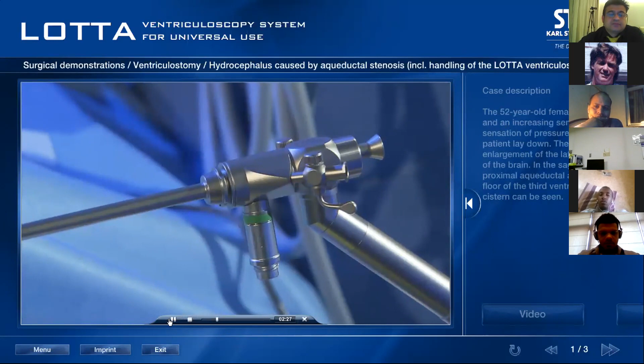However, in a therapeutic scope, because it has a working channel, we have changed 0 degree to 6 degree. Why we have done that? Because when the surgeon is putting an instrument, the issue in an endoscopic image is you are working in 2 dimension. I mean, you are seeing in 3D but working in 2D. So when you are working in 2D, you are not able to get a depth perception. So when you insert the instrument, which is just coming at the tip, the surgeon has to wait literally 1 centimeter, the instrument comes out, and then you can see the instrument has come out. So that depth perception is missing. So it is important to have depth perception. So we moved it to 6 degrees. So the moment the instrument comes out, it gives you a further extra angle of 6 degree laterally, and you can see your instrument has come out. So that's the advantage. So seeing in 2D and working in 3D.